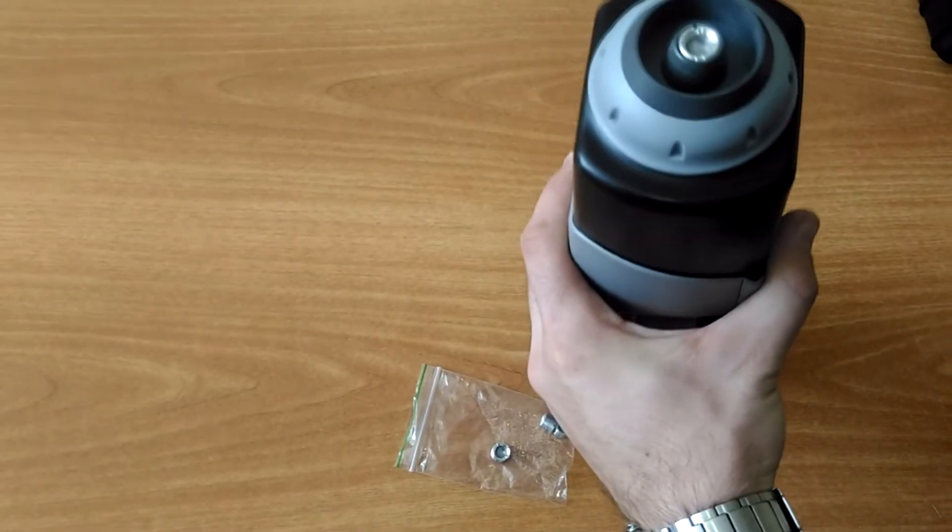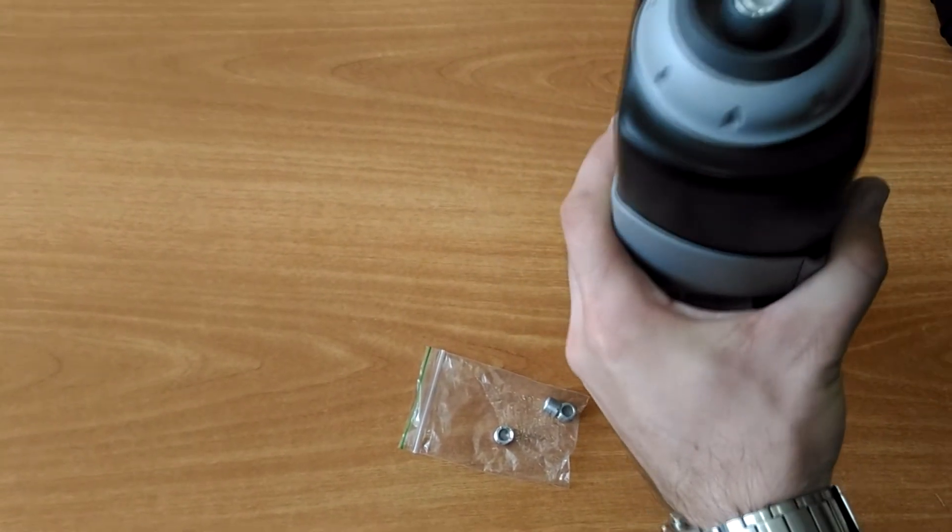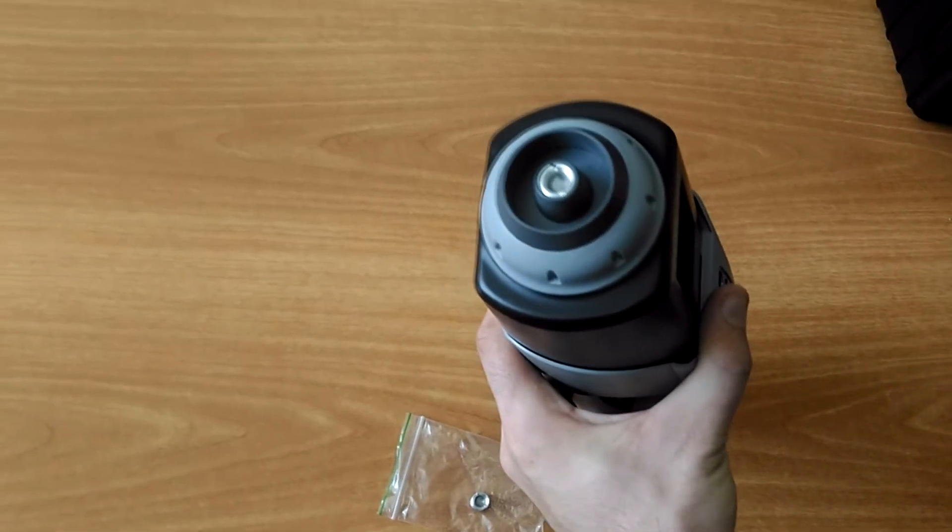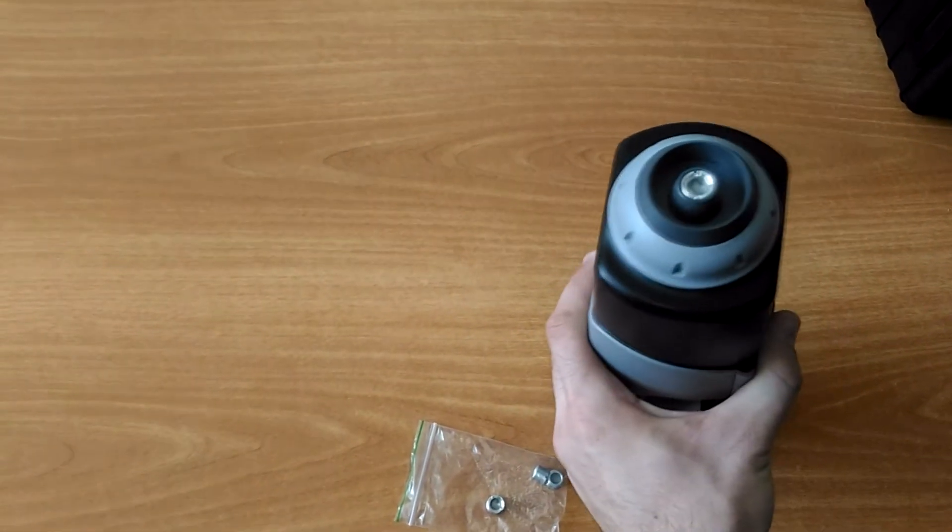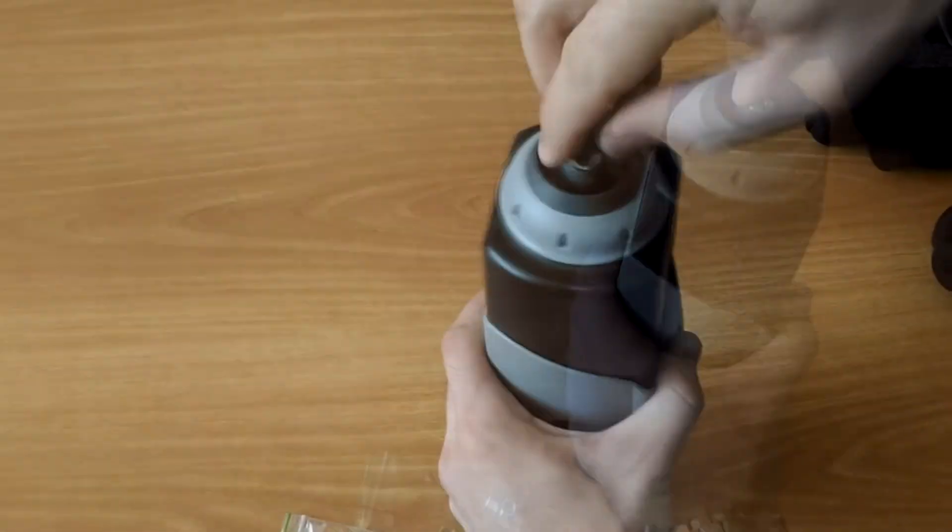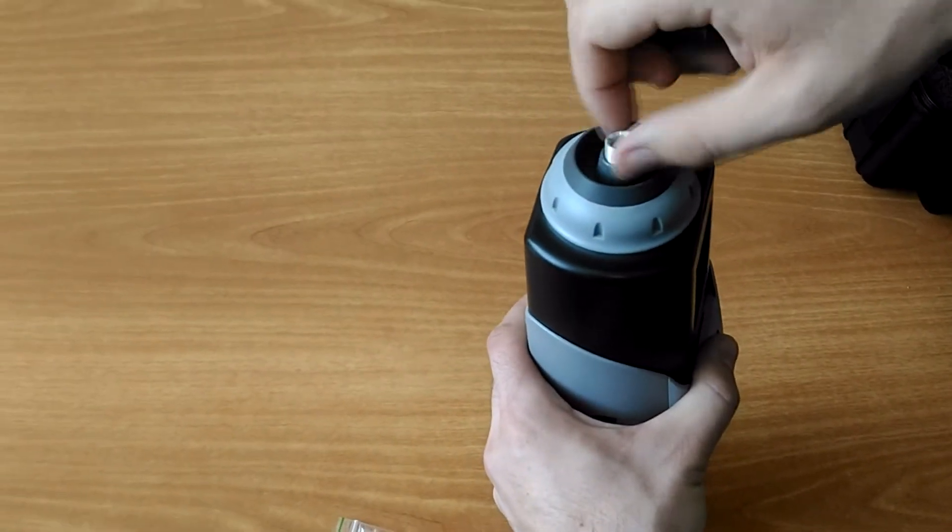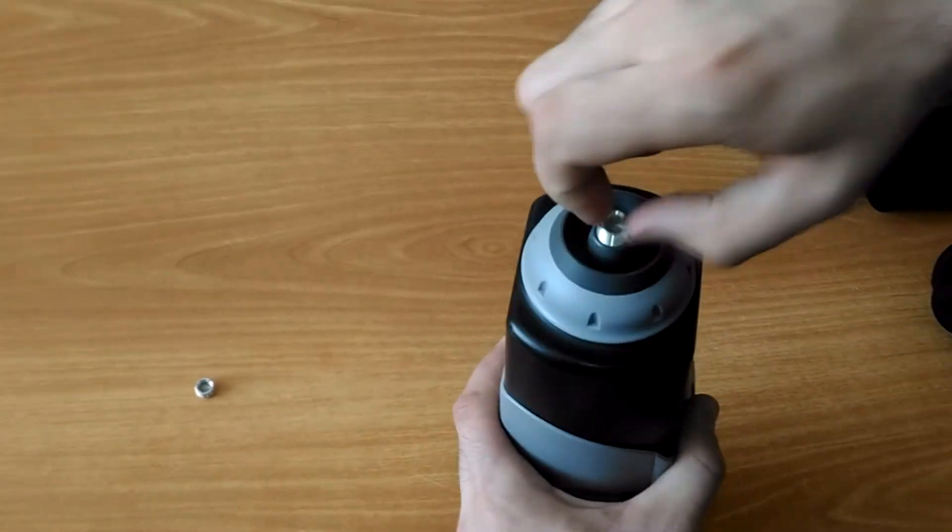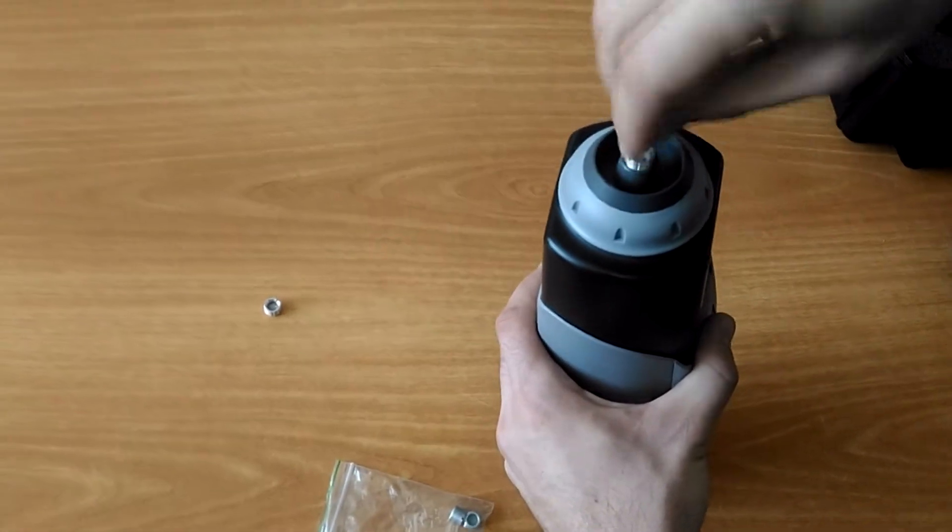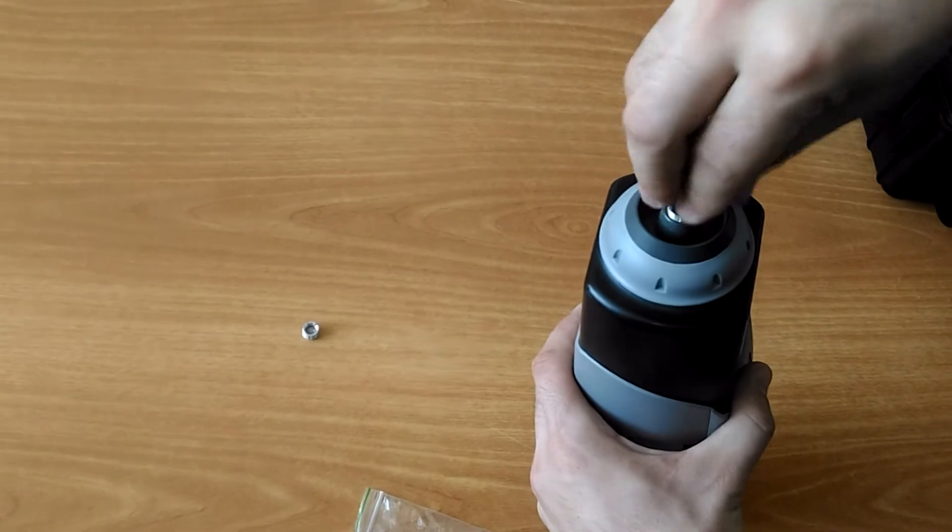If the filter grid is clogged and it is necessary to promptly continue detection, replace the filter grid. There are 3 additional grids in the delivery set. Unscrew the grid with help of key and screw the new one. Later, the used grid should be rinsed with alcohol and water.